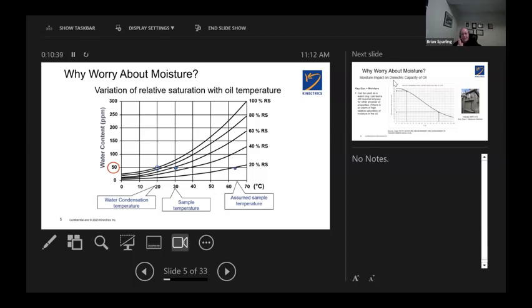When the laboratory does that Karl Fischer test, it measures absolute water content in that oil sample, and the absolute water content consists of three parts. It's the relative saturation, in other words, the moisture dissolved in the oil. It measures bound water, the water molecules that have attached themselves to things like acids, particles that may be floating around in the oil, or cellulose fibers floating around in the oil, or free water. So it measures three things: absolute water content in the oil. The interest from a moisture point of view in transformers is the relative saturation, because the bound water doesn't move. It stays there. It's never going to move.